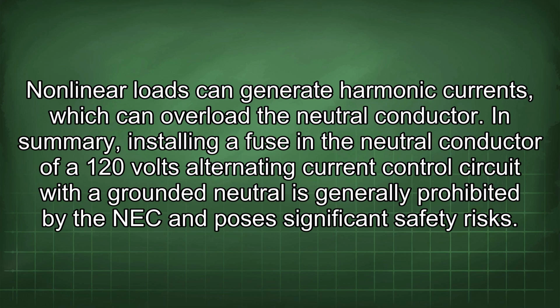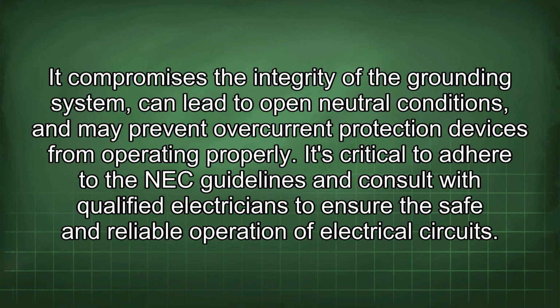In summary, installing a fuse in the neutral conductor of a 120 volts alternating current control circuit with a grounded neutral is generally prohibited by the NEC and poses significant safety risks. It compromises the integrity of the grounding system, can lead to open neutral conditions, and may prevent overcurrent protection devices from operating properly. It's critical to adhere to the NEC guidelines and consult with qualified electricians to ensure the safe and reliable operation of electrical circuits.